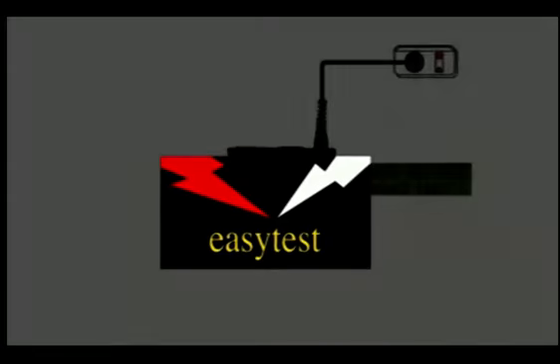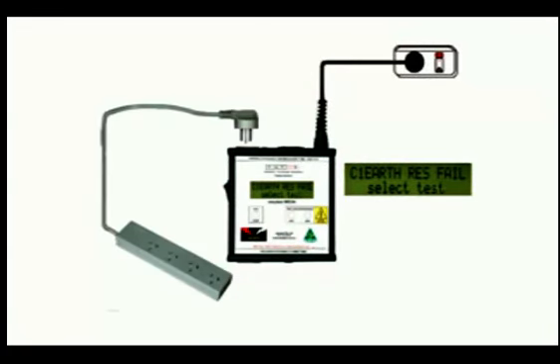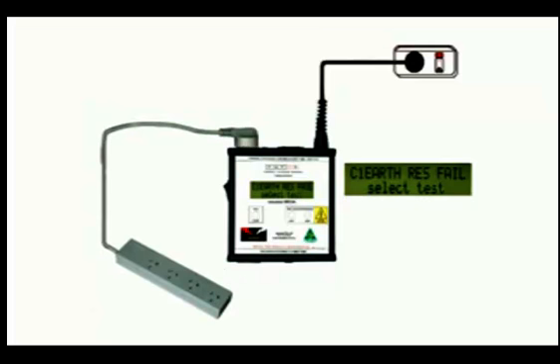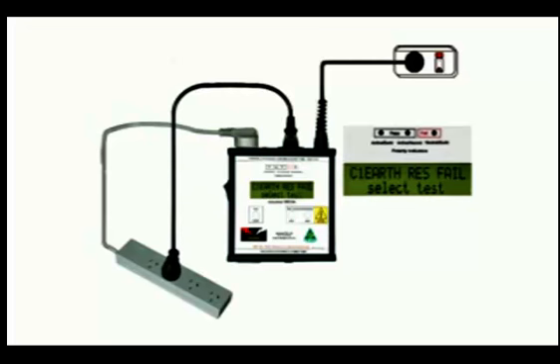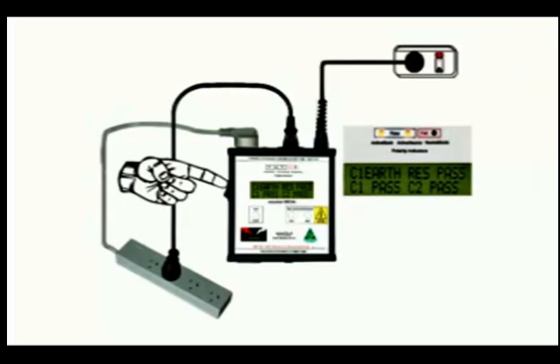We're going to test an extension lead. In this case it's a distribution board. So plug that into the top socket of the Mega. And we'll need the IEC lead to complete the circuit. Switch the power on and the Mega immediately shows all the results, all the tests having been completed simultaneously. And as long as it's plugged in, it's continuing to measure.